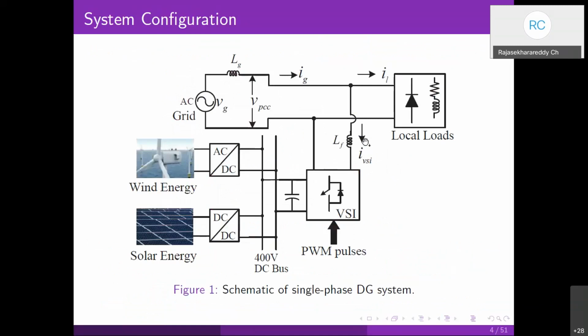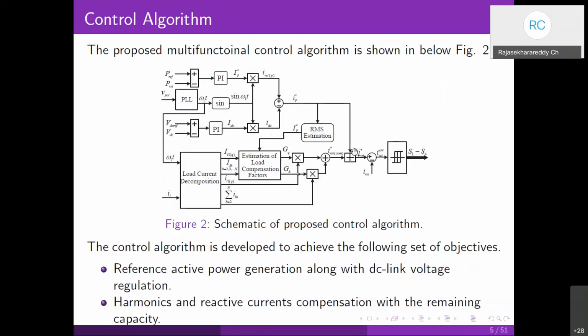You see here the actual current for the voltage source inverter is IVSI, and the reference signal for the voltage source inverter is I star VSI. The main objective is to find this IVSI in such a way that it will fulfill all its objectives. If you look at this control algorithm, it has the following set of objectives. One is reference active power generation along with DC link voltage regulation, and the second objective is harmonic and reactive current compensation with the remaining capacity of the voltage source inverter.